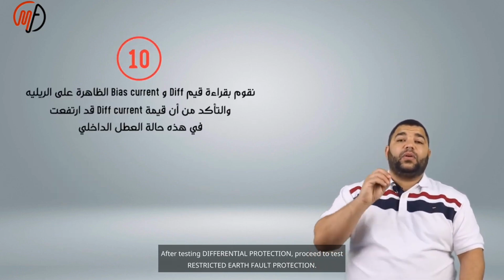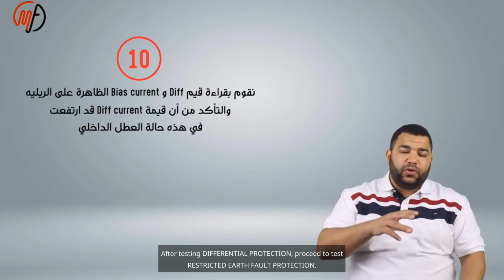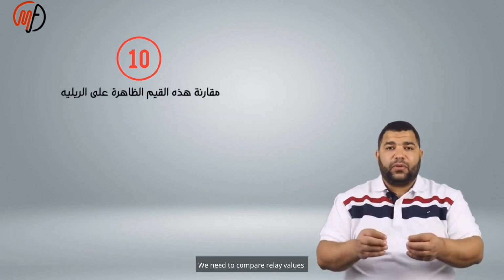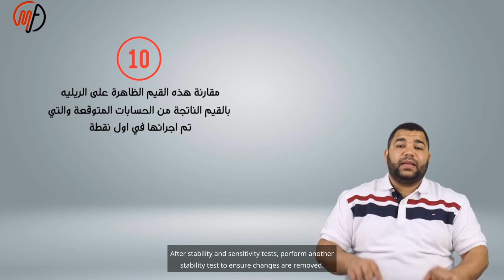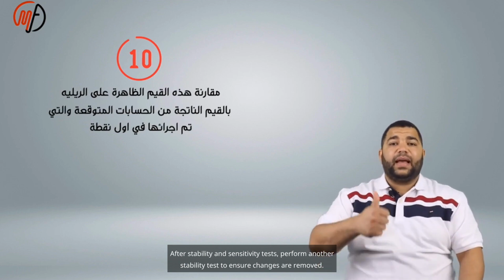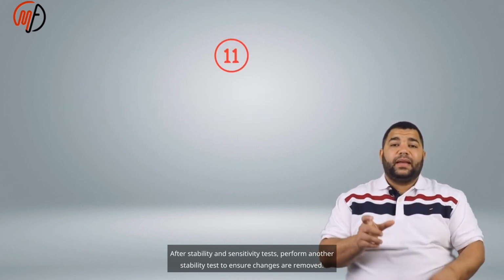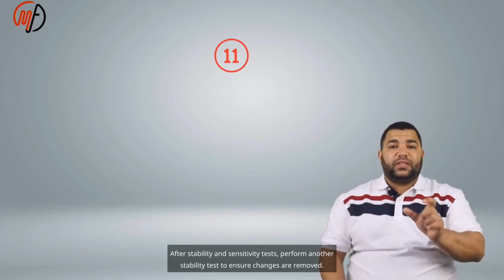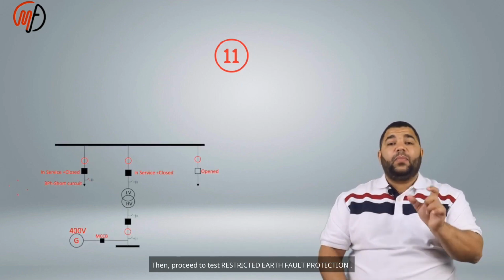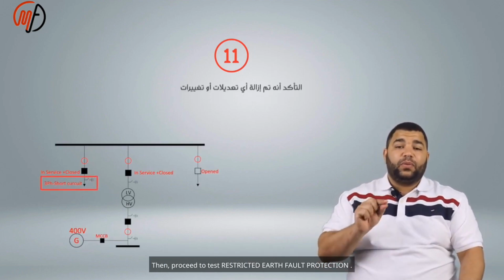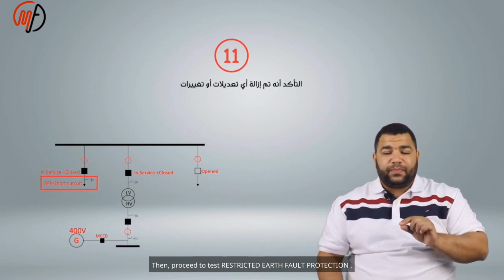After testing differential protection, proceed to test restricted earth fault protection. We need to compare relay values. After the stability and sensitivity tests, perform another stability test to ensure the changes are removed. Then proceed to test restricted earth fault protection.